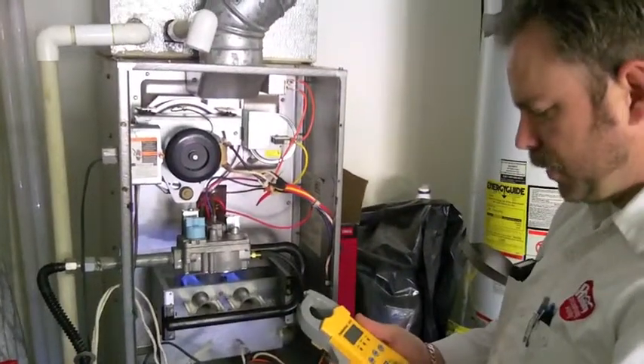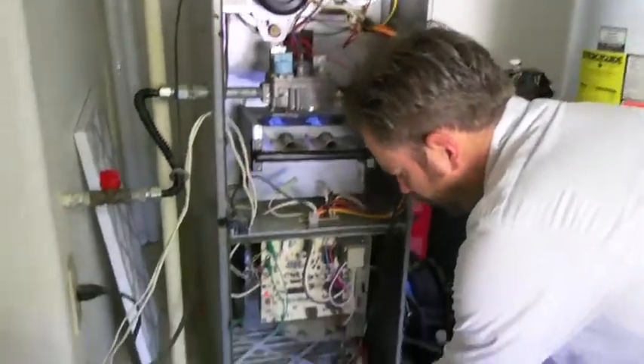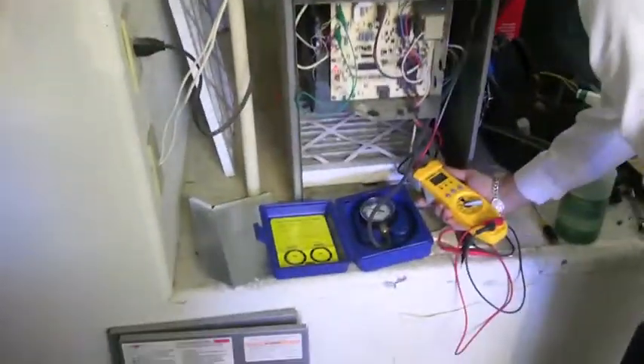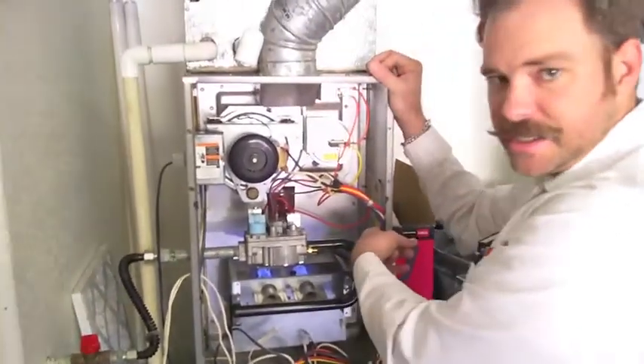Now I'm going to get an amp draw on the motor. We're running about 3.2. Now you can find all of your ranges for this equipment on the tag that's inside of the furnace here.